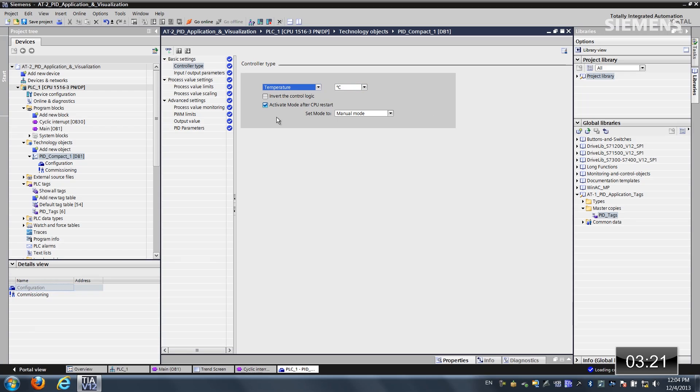And this is the version 2 PID compact. It has a couple of differences, one of which is right here. The set mode to, we can actually change it to automatic mode. That way, if you go from start to stop or power cycle it, it always goes to automatic mode and starts up immediately.